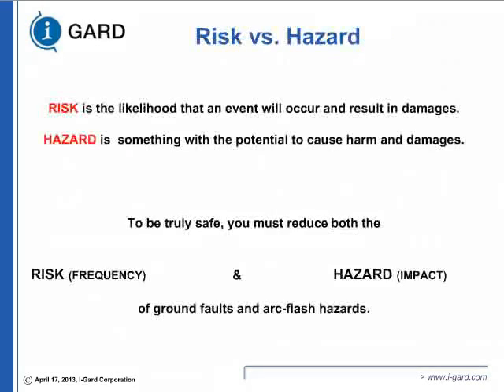So how do you do that? It's very hard to remove a hazard. You have to consider risk and try to minimize or eliminate the risk. Risk is the likelihood that an event will occur. Hazard is something that's a potential cause of harm and damage. To be truly safe, you should try to remove the hazard first, if you can, and then worry about the risk. Now, just to give you an example, most of you are familiar with ground fault circuit interrupters. They do not remove the hazard. They remove the risk. So risk, by definition, is always dependent on proper application of a protective device.